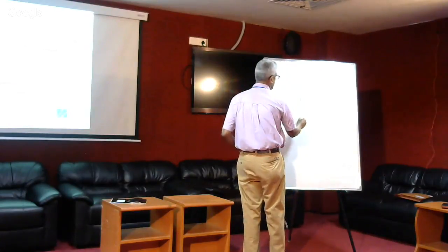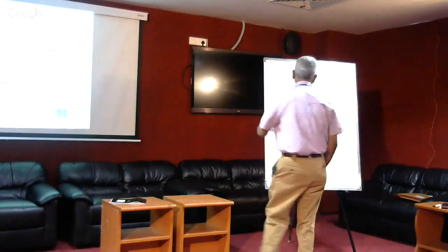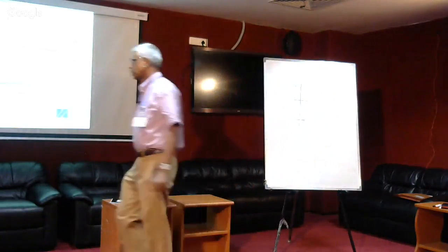So here, the number of bed volumes to breakthrough is very high. Here, if this is 0.5, that means all this column is unusable. Now, whether that is because of a first order or second order, that's not what I am getting at. Whether it is first order or second order, you can have this kind of a slow bleed. But we need to watch out for this because if this is the case, then you may have to increase your EBCT or things like that.